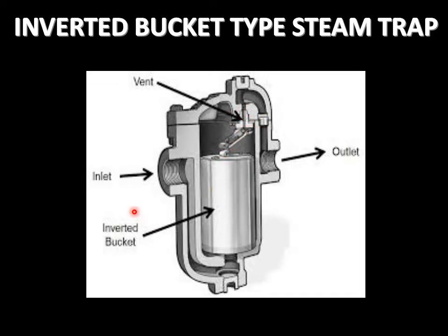Now initially, when the entire body of the steam trap and the bucket is filled with steam condensate, the bucket will be submerged. In this position, this port will be opened, so as more and more steam enters and gets condensed, the condensate will flow through this port.